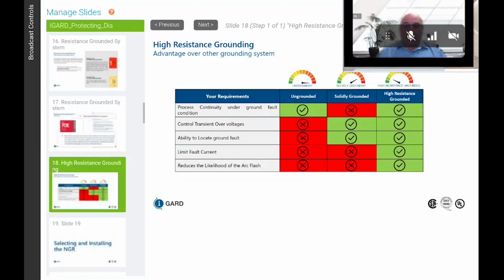So when we look at the grounding systems available, you have an ungrounded system, a solidly grounded system, and a resistance grounded system. For process continuity under ground fault, ungrounded systems do a great job. You don't have ground fault protection with an ungrounded system; you have ground fault detection, but you lose out on controlling transient overvoltages, the ability to locate the fault, limiting fault current, and reducing the likelihood of an arc flash.